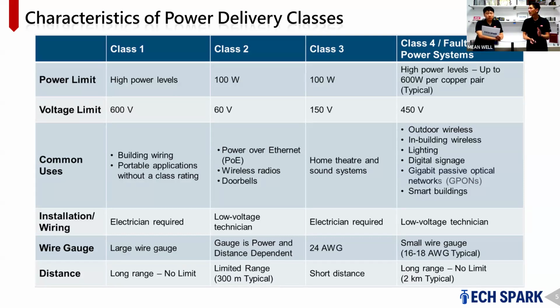For lighting, people wanted Class 2, and then there's Class 1 and Class 3, which require different voltages. Class 1 is like 600 volts, like building wire, and requires an electrician to do the installation. Class 3 is higher voltage but lower power, still requires an electrician to install and requires conduit, but the wire gauge used can be as small as 24 gauge.